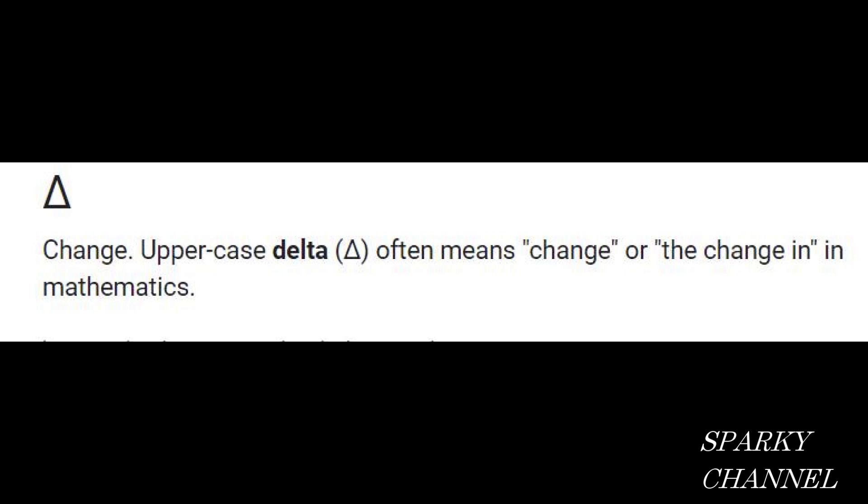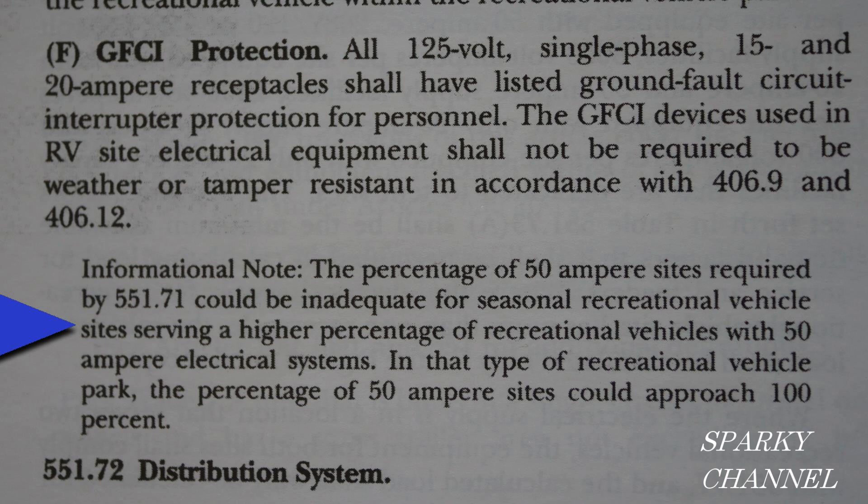In case you're curious, the uppercase delta symbol often means change, or the change in, in mathematics. The indented note with slightly smaller text is an informational note, also called a fine print note, which contains explanatory material intended to clarify a rule or give assistance, but it is not a code requirement.